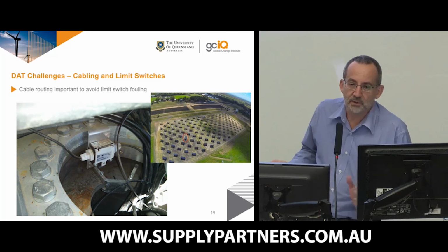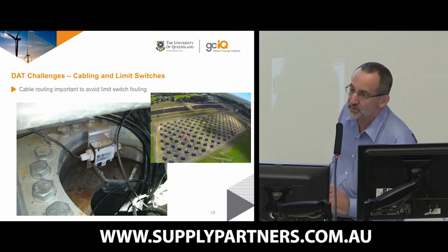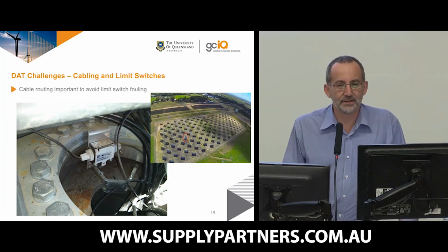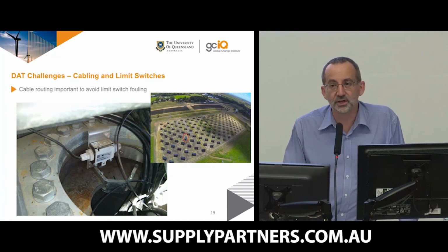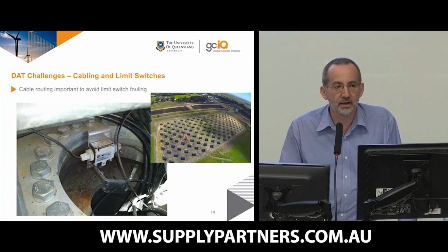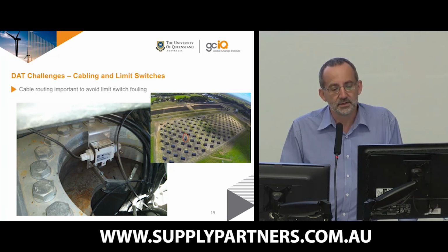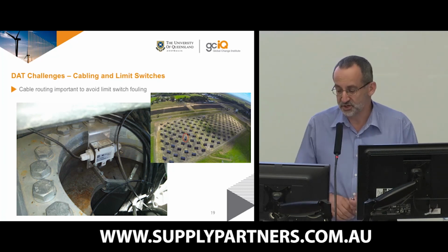But what we did find was happening is that all these cables running up through the middle were fouling the limit switch and causing it to stop. And as a result of that, unfortunately, our dual axis array has been stowed since March and is still waiting remedy. So that has proved an interesting challenge.